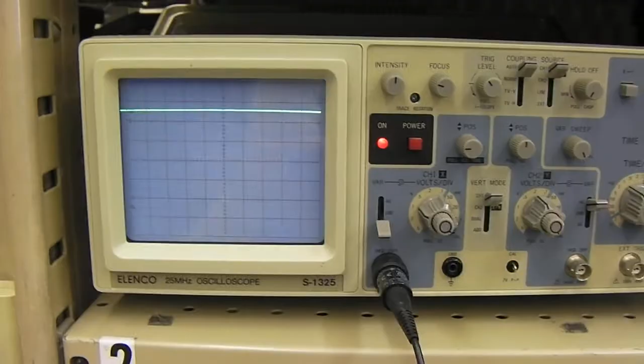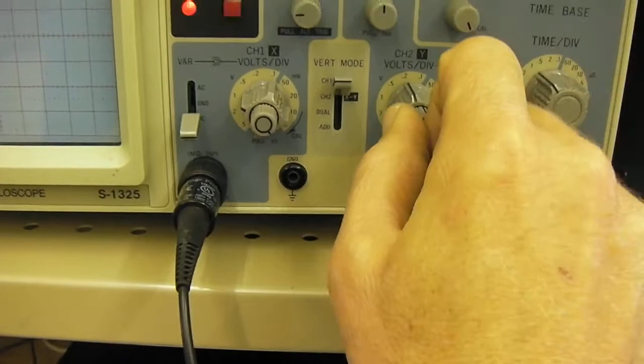Okay, now let's go back to our instructions here, and it says to set the vertical and horizontal sweep control knobs to the calibrated position where it clicks. These knobs are mostly found inside the volts per division and time per division controls. So what we're talking about there is these knobs right here. These knobs are for calibration, and we normally want to have these where they click. So those are set where they click.